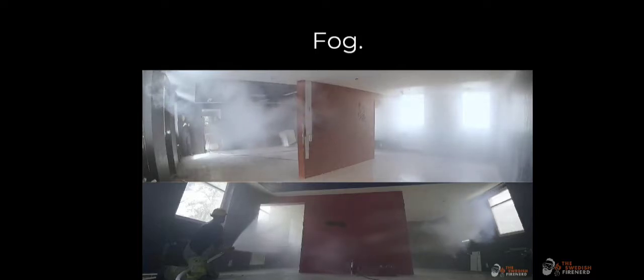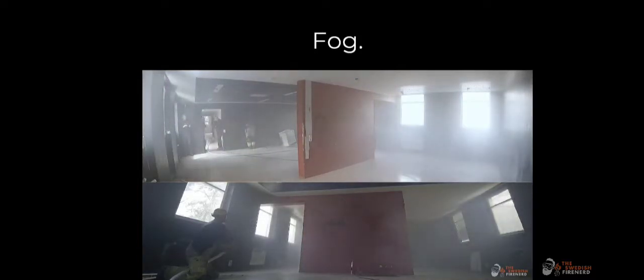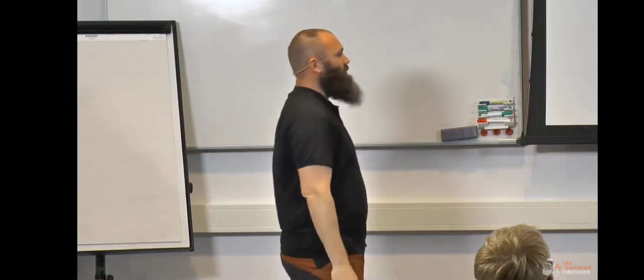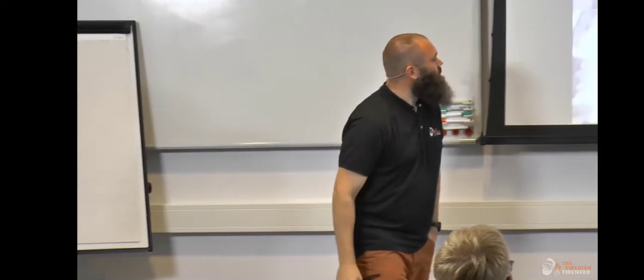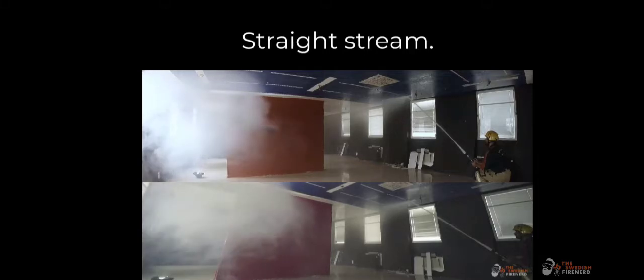But if you have an open space, if you put a fog in, things will move over here. It will push things over here, and we will push things somewhere else if we don't have an outlet. Maybe it's into another room. Maybe it's back to ourselves if it's a U shape like this, which is the same for a straight stream. If you put it in a ceiling here, you will move air over here, because in front of the stream there will be an overpressure, and the overpressure pushes everything here, and you start to rotate everything.